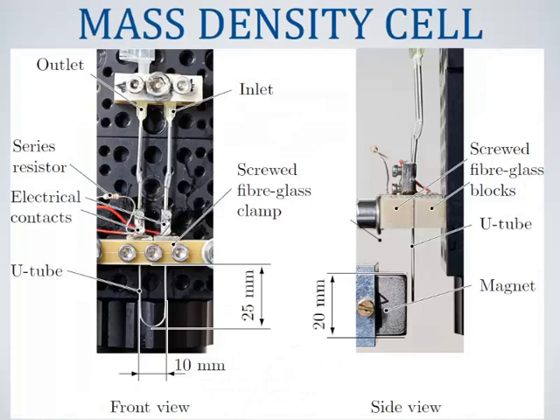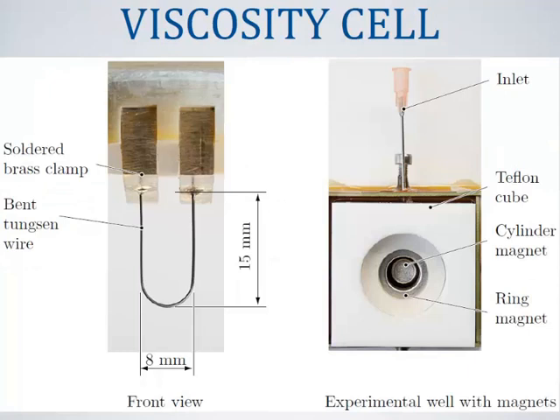This is a photograph of the mass density sensor. Here we see the stainless steel tube which is clamped by two fiberglass blocks. Here you see the permanent magnet which we use for the magnetic field. This is a picture of a first viscosity sensor. Here you see the 400 micron thick tungsten wire which is brazed into two solid brass blocks which is necessary to get very stable devices.